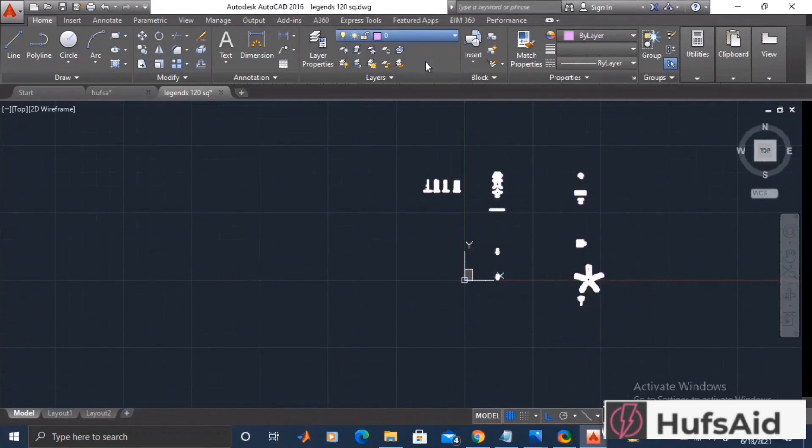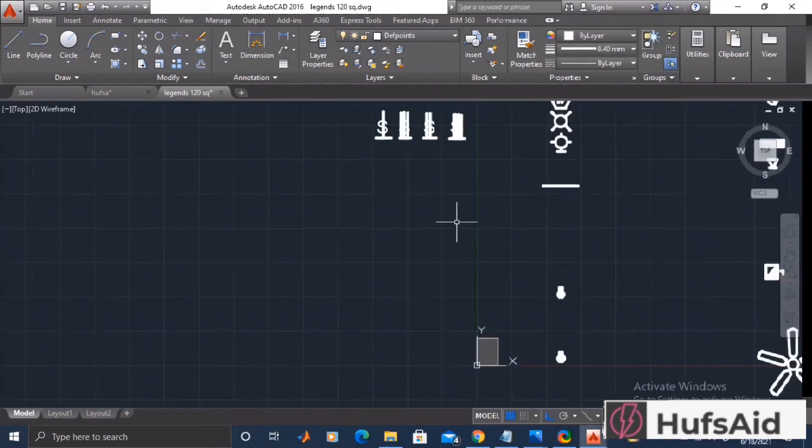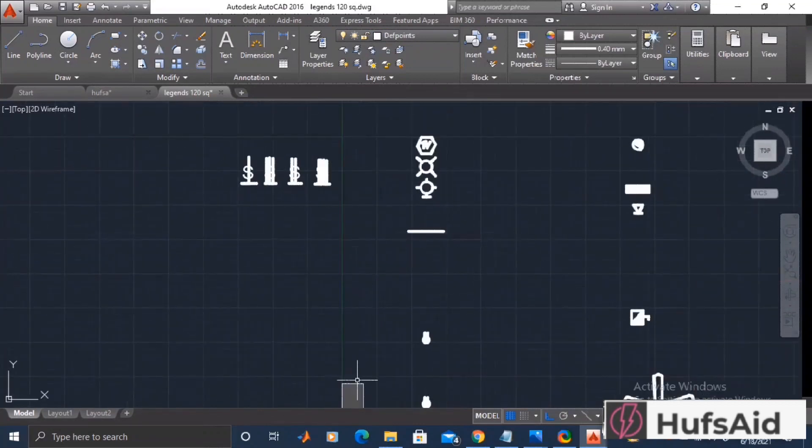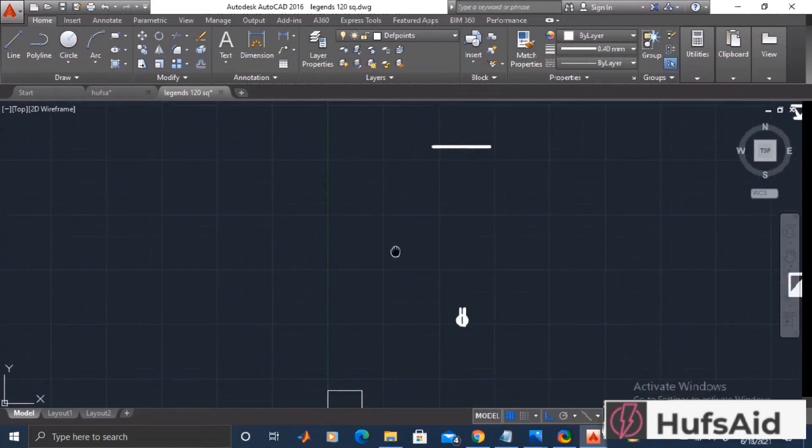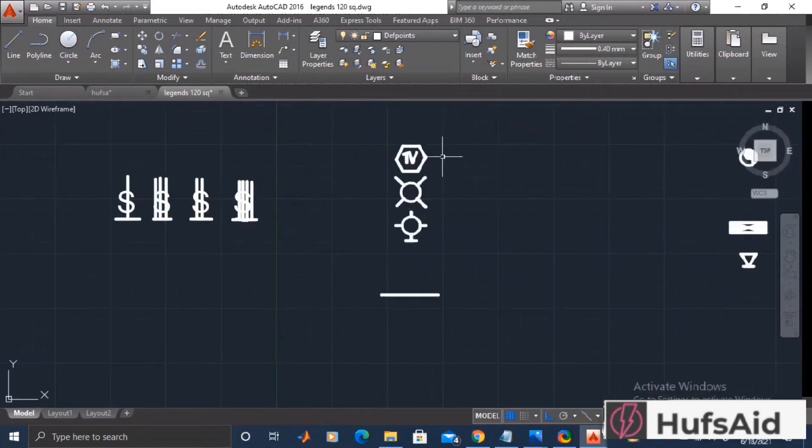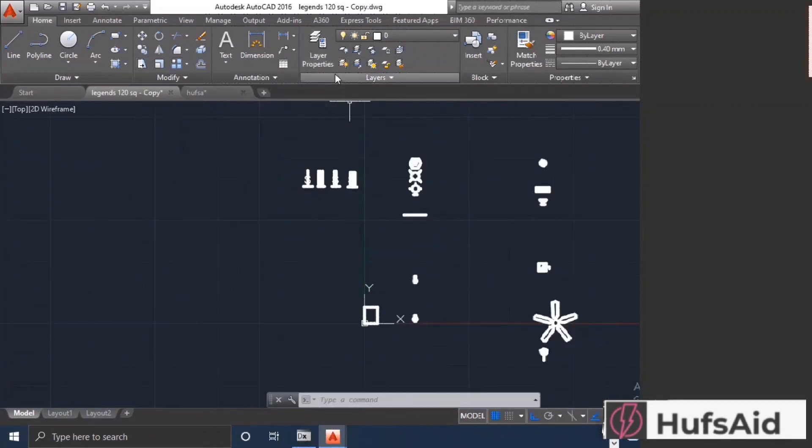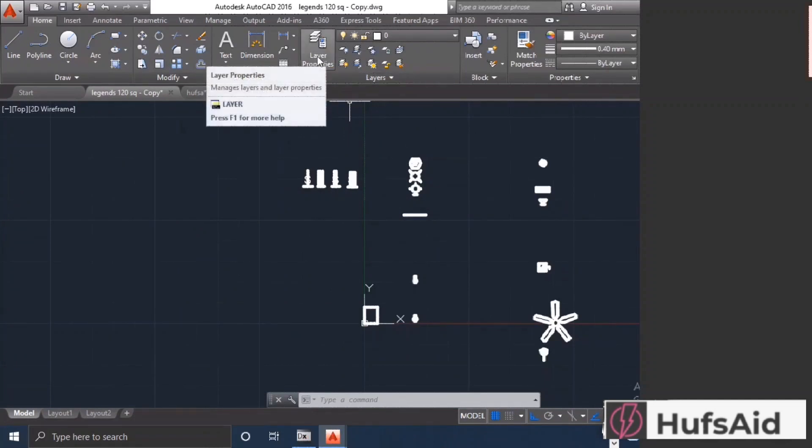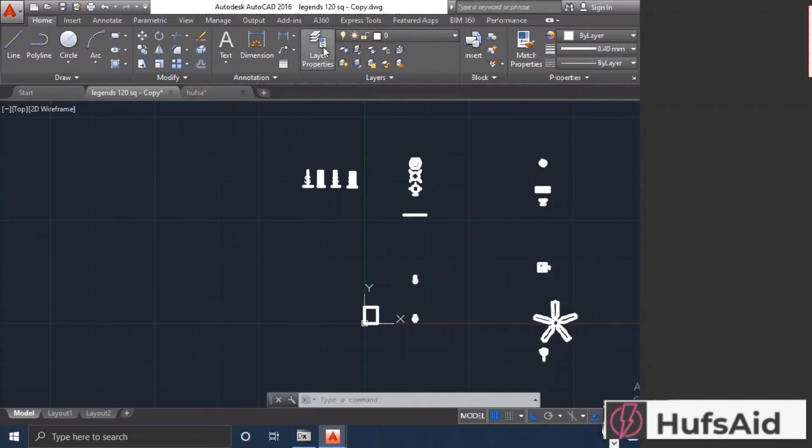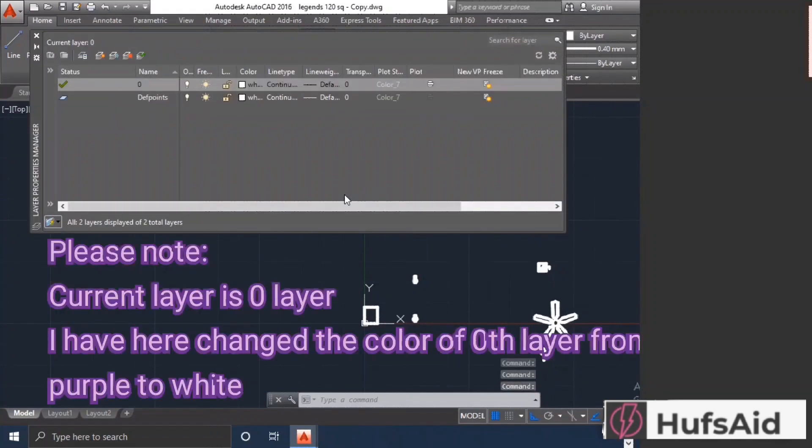If you're not using the same files of legends, then you're supposed to do that before you start making the blocks of each and every symbol. I have selected these and changed the layer to Defpoint. This is the layer you are never going to make your legends on, because if you make the legends on the Defpoint layer, then it won't show up in your printout or in your paper space. Here I have opened the layer properties and I have selected the 0th layer.